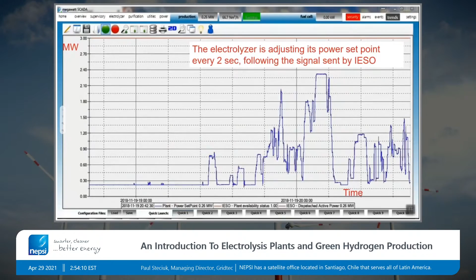And in return for doing that, we get paid by the grid operator because we provide a paid grid service. So you're actually matching power supply with power demand. Normally a generator governor changes its output to regulate power, but instead you're telling the generation facilities to hold their power constant, while the load goes up and down, and you're going up and down with the load to stabilize power consumption. Is that right? Exactly. That's exactly it.